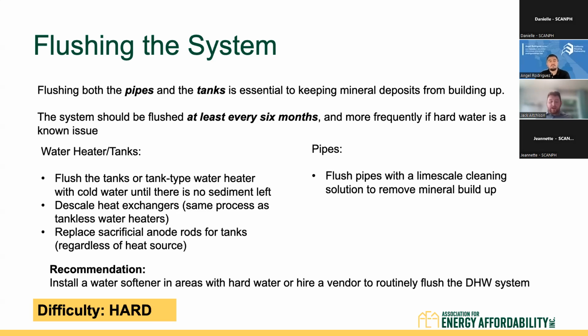They do have food grade descaling equipment or descaling chemicals that can go into your water heating system and protect the pipes as well, to avoid buildup of calcium and magnesium bicarbonate. But if you have really hard water, if you're in Southern California, you should consider installing a water softener, and you should definitely hire a vendor to routinely flush the DHW system. It's much less expensive to have a vendor come out every 6 months and flush the system than to have to replace your heat pump water heating system or your gas boiler every 5-7 years, compared to their expected useful life of 15 to 20 years.